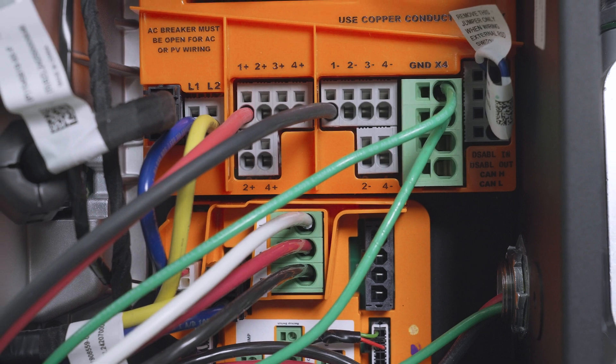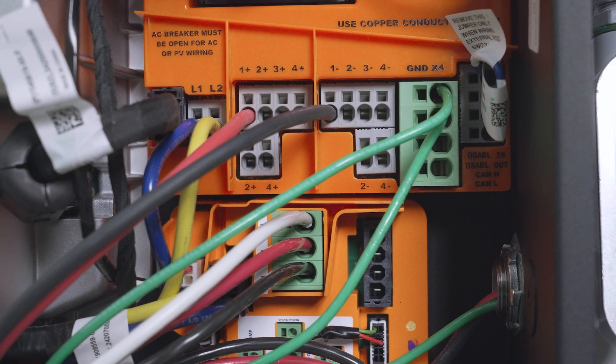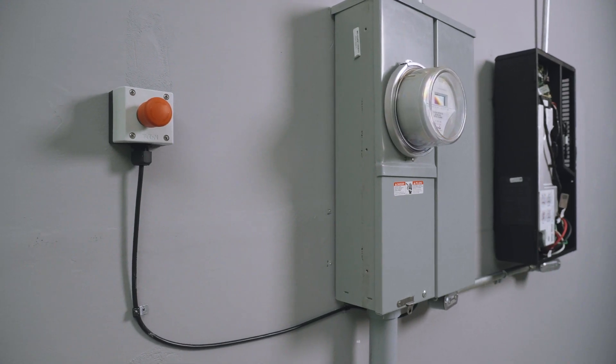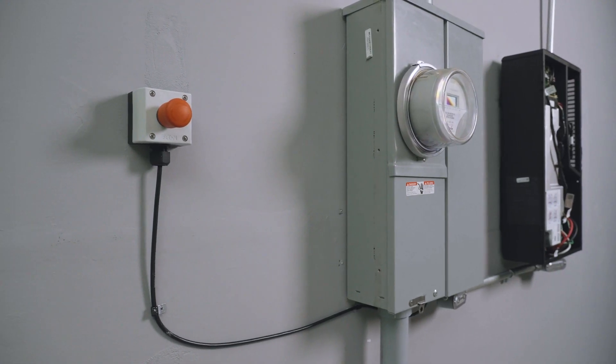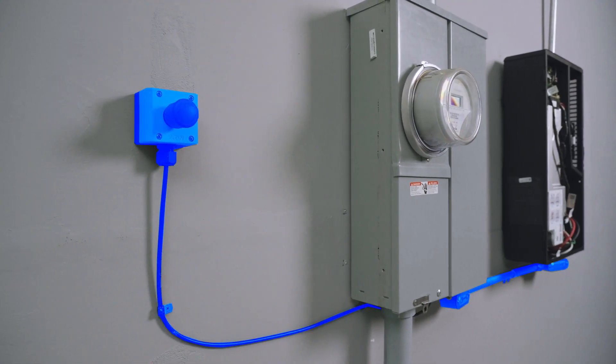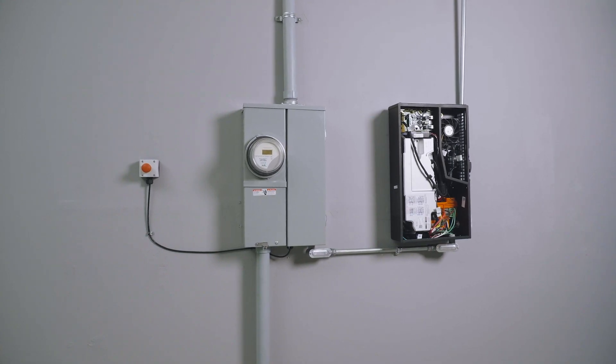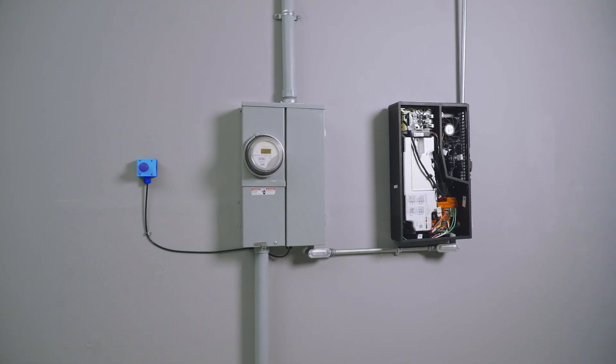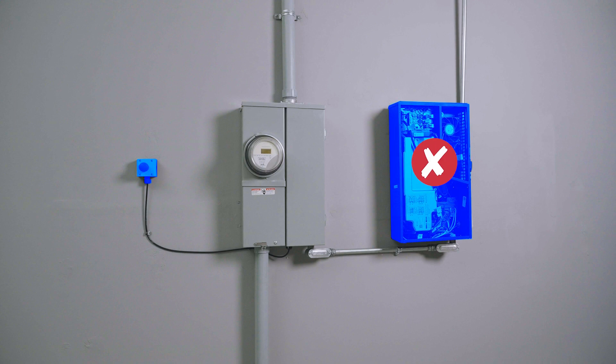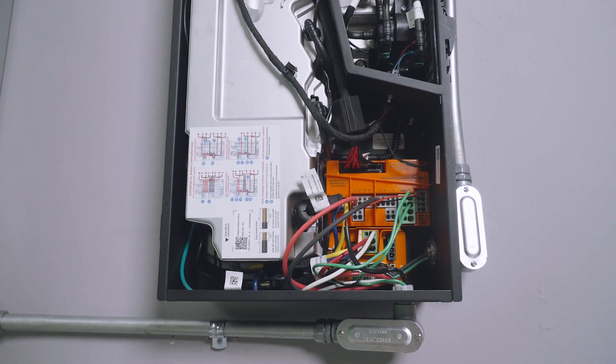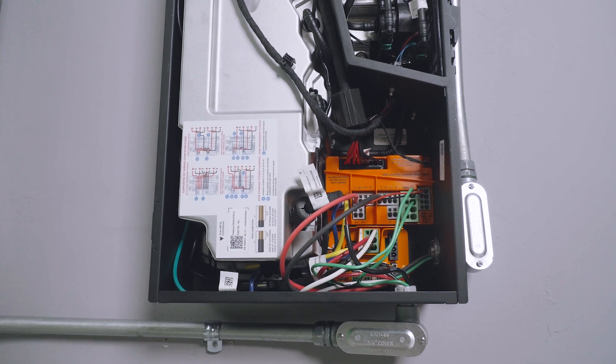In addition to the DC and AC wiring, the solar inverter can be wired to a low-voltage system shutdown switch that disables the inverter. When the system shutdown circuit is opened, the AC relay within the solar inverter is opened, disabling solar output. To install a system shutdown switch, locate and remove this factory-installed jumper between these two terminals.